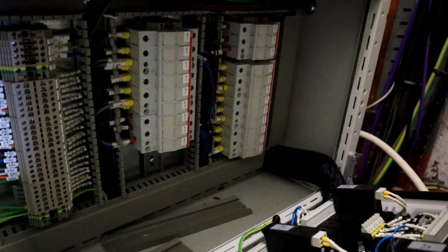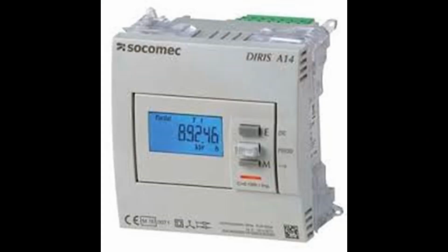We would propose reusing the existing current transformers and associated wiring. We would reuse the existing voltage references and we would replace the meter with an MID approved meter with Modbus comms that could be fitted in the same cutout in the front of the metering panel.